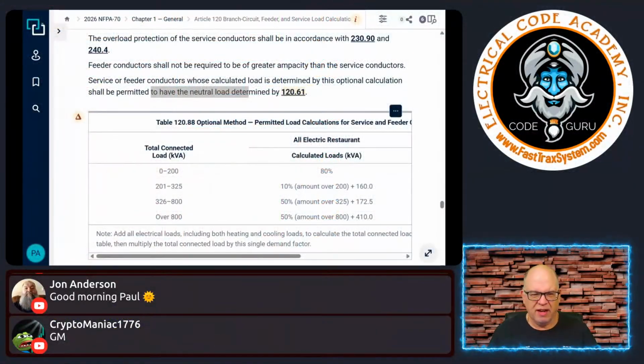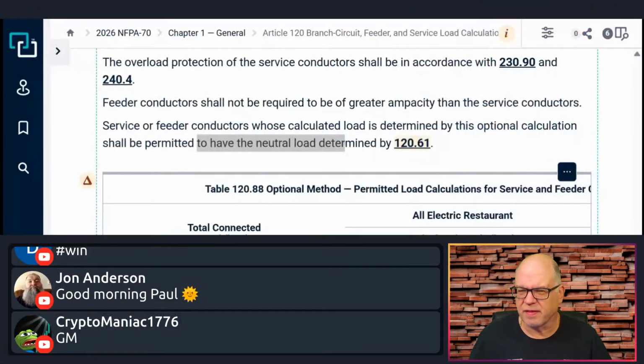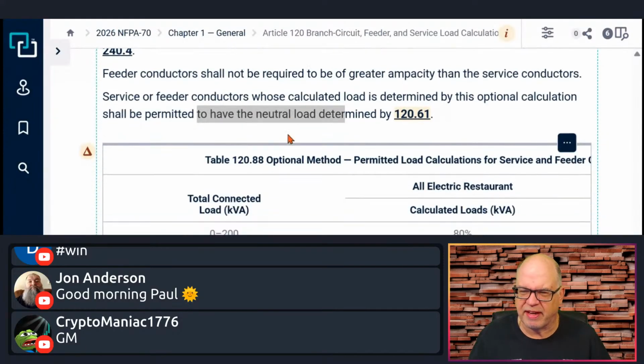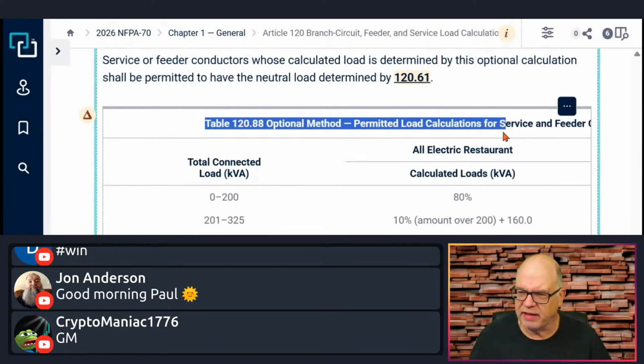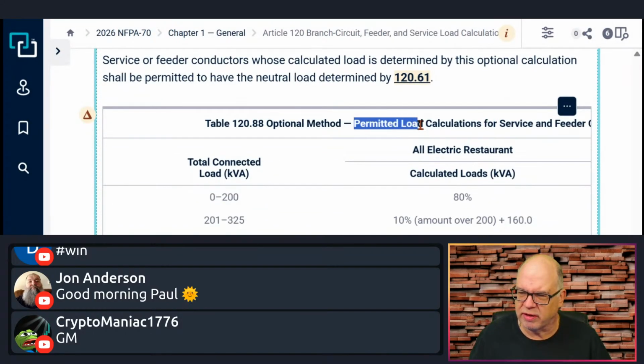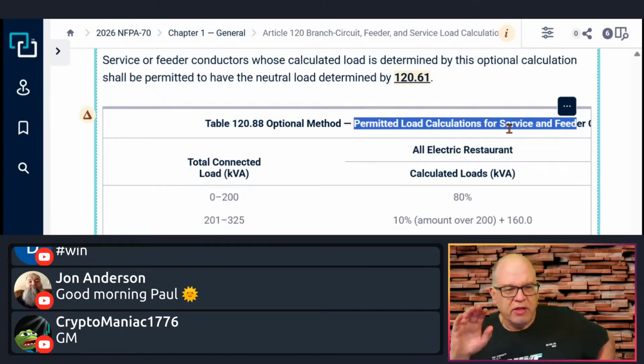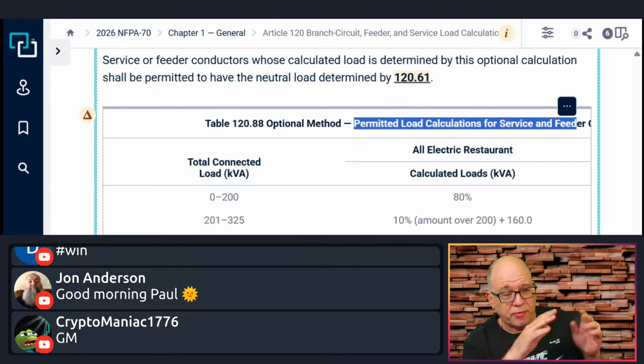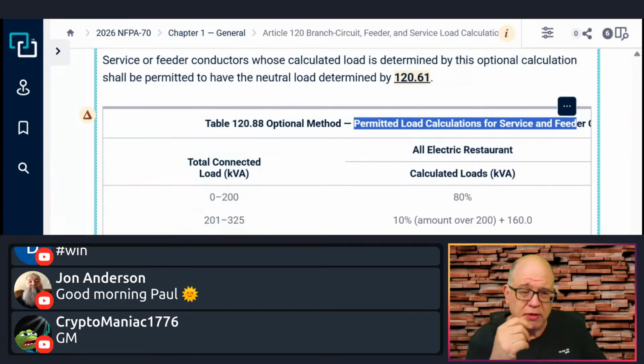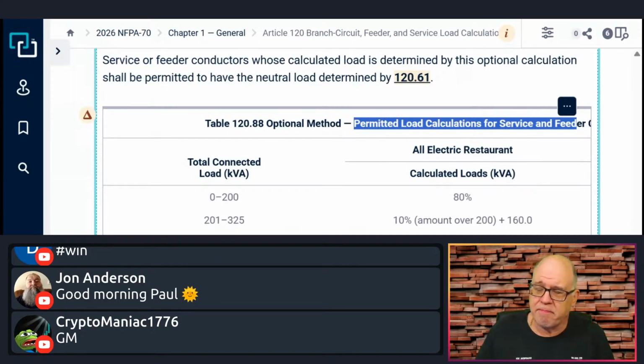Okay. All right, that one's hard to see, so let's go to the NEC. All right, so here's where we got that there. Now, here's the table. Okay, now see it says permitted load calculation for service and feeder. So you can do it using part 3 of 220 or part 4 of 220 if you choose to do so. On an exam, unless they state otherwise, you use the standard method.